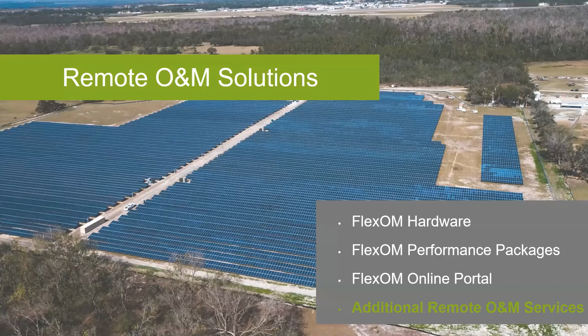These types of services, of course, are only performed with the written permission of the asset owner and the utility, for things like remote site commissioning (coming soon), upgrade firmware, site tuning assistance, inverter setting changes, field site issues and diagnostics, a site health check, and items like utility grade setting changes of power factor and protective settings like grid voltage trip and clearing times or grid frequency trip and clearing times to meet utility requirements.